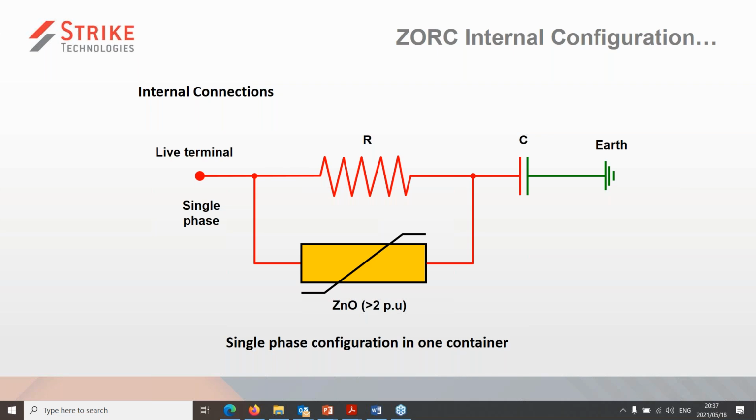In doing so, the 30 ohm resistor would then match that surge impedance, as opposed to no protection device being in place, where your high frequency transient that is generated from your switching activity would go along and meet a very high impedance on the load side of a particular winding on the transformer. Obviously having an impedance that is much higher would then cause that transient needing to go somewhere, where you start having the ringing effect, voltage doubling, voltages coming back, reigniting in the contact gap of the switch, etc. And this is where you have your multiple re and pre-strike conditions.